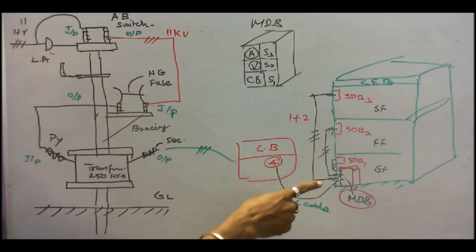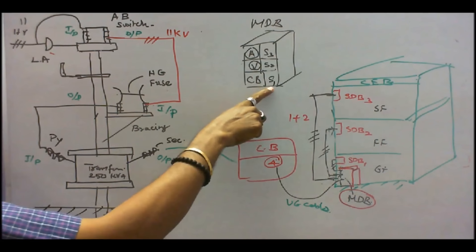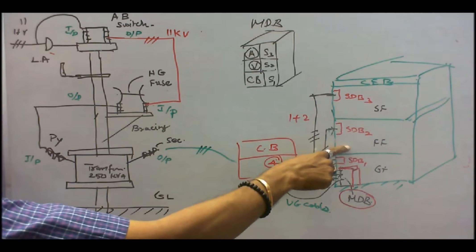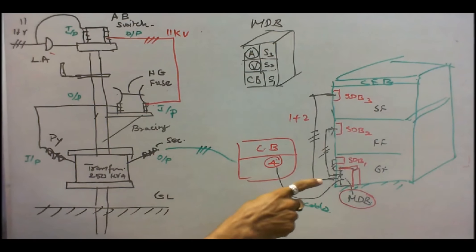Suppose I want to switch off the ground floor for maintenance work, simply I can switch off S1. The power will not be available. Power will be available in the first floor and the second floor. Here the main distribution board acts as a distributor. These all act as feeders. This is the basic difference between a distributor and a feeder.